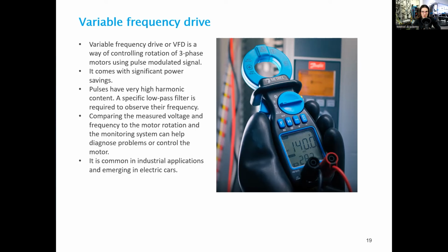Now, these pulses, as I mentioned already earlier, have very high harmonic content. They reach very high frequencies, and a specific low-pass filter is required to observe their frequency and their effective voltage. Now, the relevant part of the signal is usually close to the first harmonic, somewhere in the 30 to 60 Hertz range. But the VFD filter is usually set up a bit higher to accommodate any outliers. So the VFD filter is a low-pass filter that will show us only the relevant part of this modulated pulsed signal. This application will be found in industrial motors, and it is ever more common in electric cars.